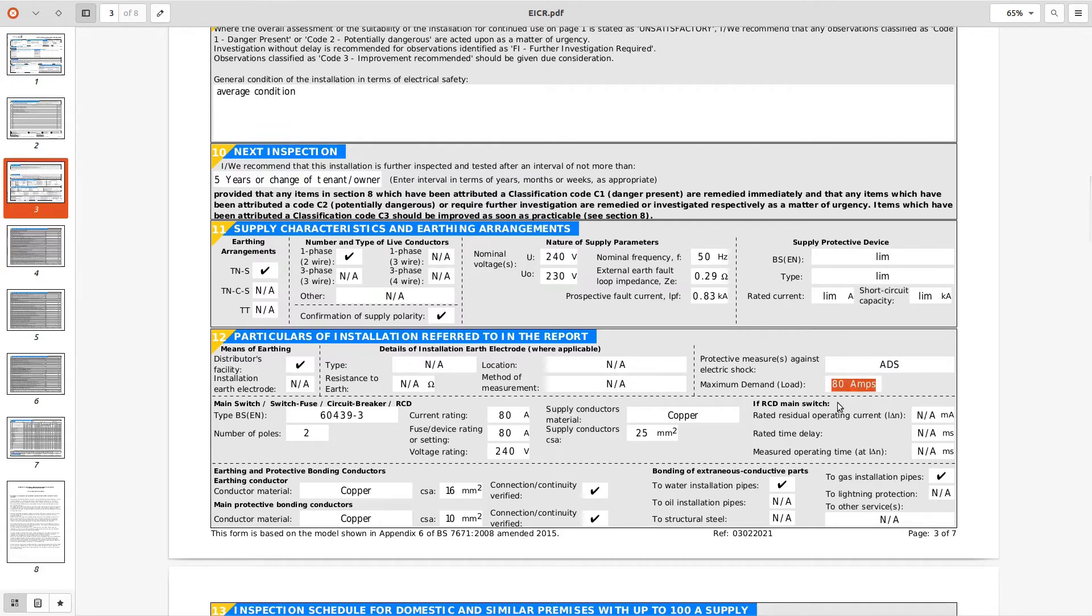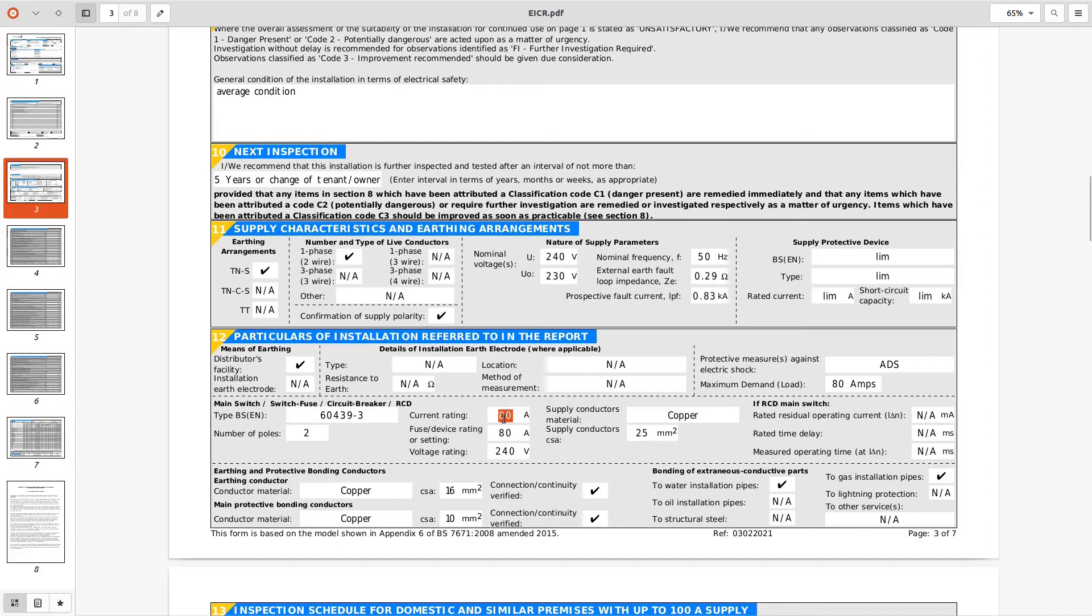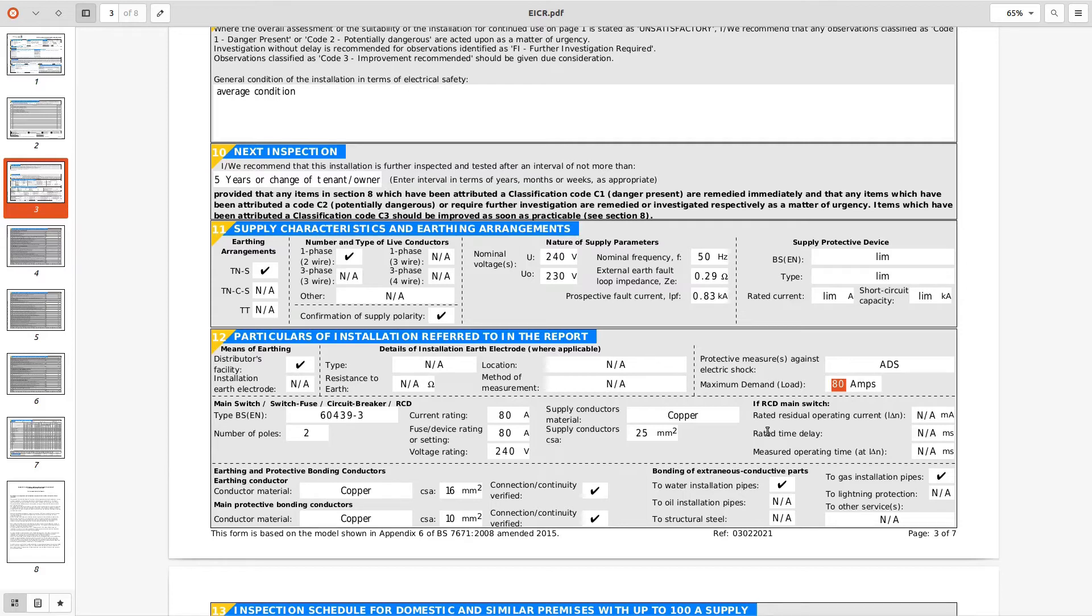Maximum demand 80 amps, never going to be 80 amps there because we've got a current rating of 80 amps on that, so they've taken the figure from the main switch and put it into this thing here. Should be clamping these if practical or calculate, look at your circuits, don't add them all up because that's not a true maximum demand. You're never going to use everything and take a percentage of what you think is real. So this figure would may have been in the 50s I would have thought looking at the circuit identifications that we'll come to shortly.